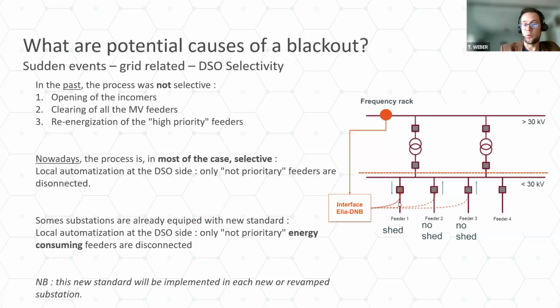So today, in our new substations, and every new or revamped substation, the same standard is implemented. It means that we are selective, and we also make a real-time calculation in the IED, the intelligent electronic device, typically the protection relay. Just before tripping, the protection device is calculating: am I consuming or am I producing energy? If I am producing energy, I will not trip. If I am consuming energy, I will trip. So in this case, we are sure that we only disconnect load. That's the new standard that is implemented in all substations. Before, it was not selective. Today we are selective, and we are implementing selectivity with the direction of the power flow.